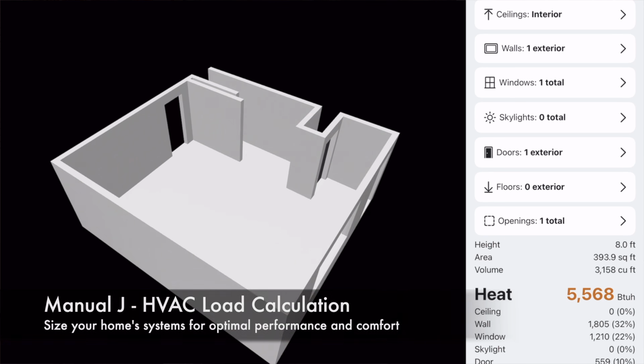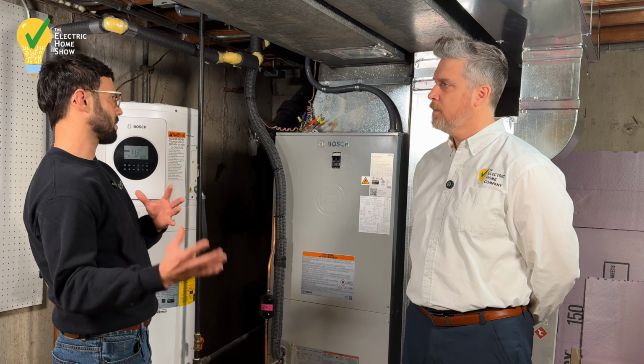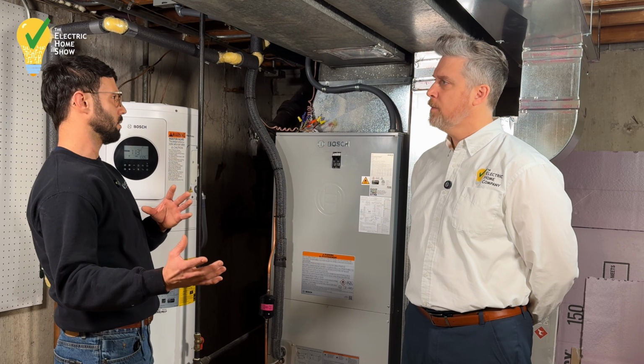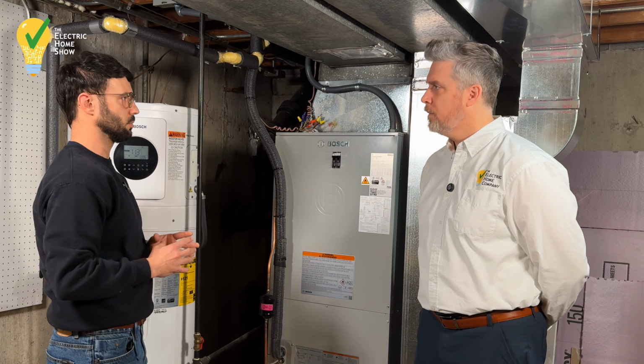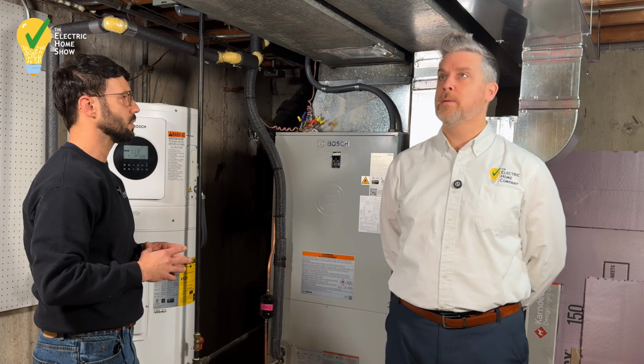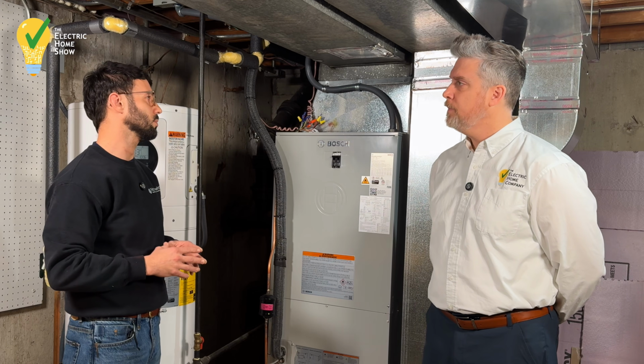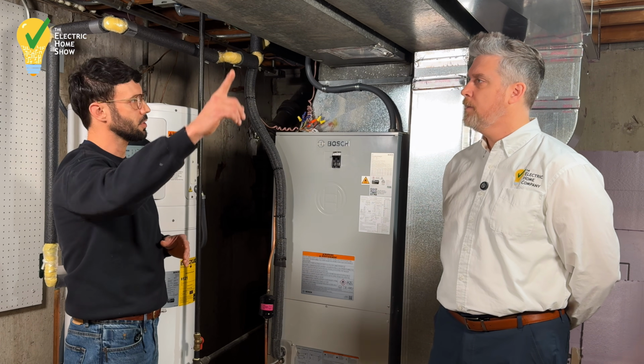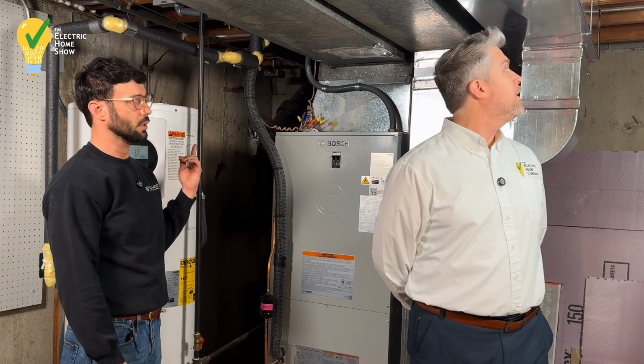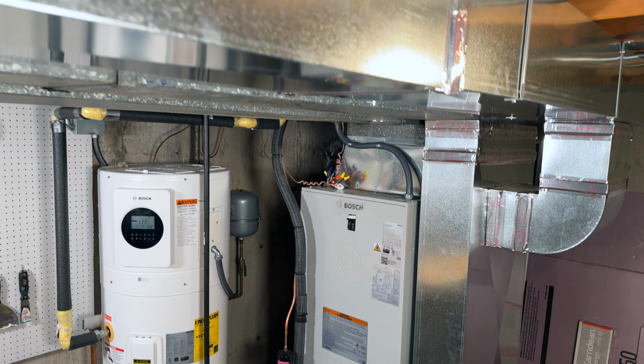Right away, we matched that load calculation and compared it to the ductwork. We found that it was undersized, so we had to increase the size of the return and modify some of the ductwork upstairs to ensure that a heat pump system would work for them.